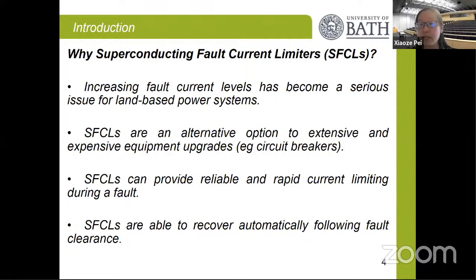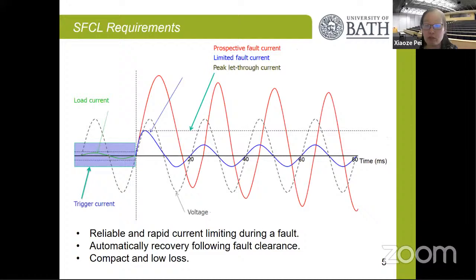The option is, firstly, you can consider upgrading all the circuit breakers in your substation, but this is very expensive and also a lot of civil engineering work is involved. Or the superconducting fault current limiter is a new technology that is able to limit the fault current level. So you only need to put this unit into your grid, and then the rest of the system can remain the same. So the requirement for a superconducting fault current limiter is that it has to provide very reliable and very rapid current limitation during the fault. And when the fault is cleared, it needs to have the functionality to recover automatically from the fault condition as well. So this is a typical requirement for a superconducting fault current limiter.